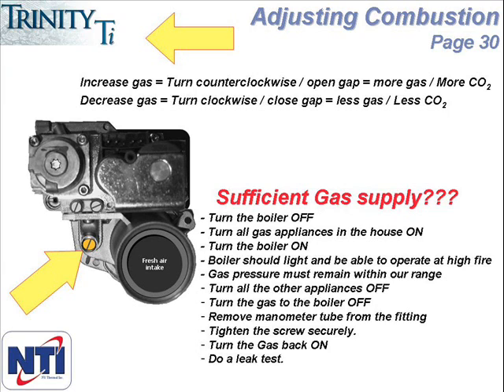Once you've confirmed this is the case, turn off all the other appliances, turn off the gas to the boiler, remove your manometer tube, then make sure you securely tighten the screw on the line pressure port. Once that is done, do a leak test to make sure everything is properly sealed.